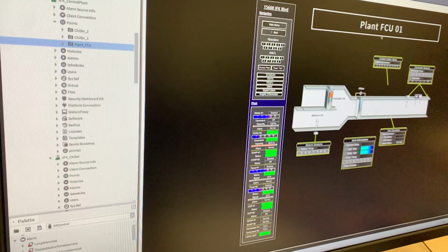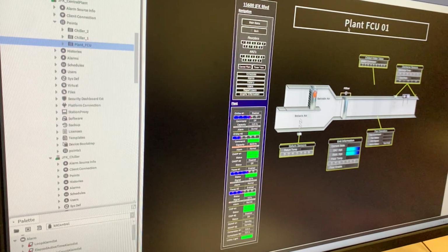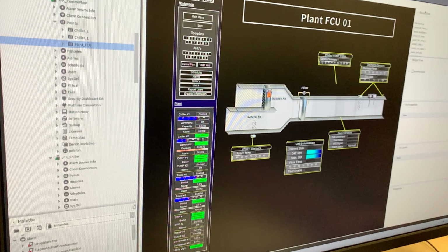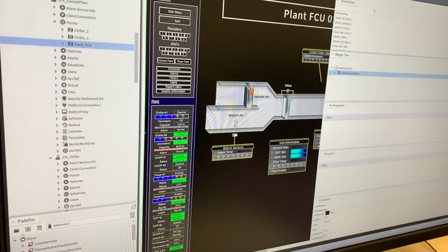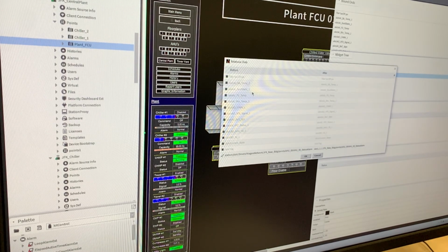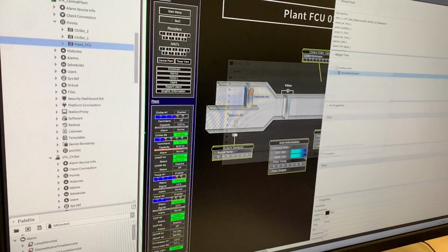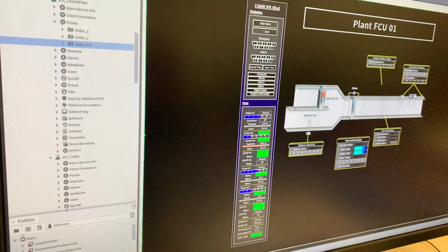When you do a VAV box or a fan power box through Honeywell, the point gives you a tag already built in, to where you can just link it and then relativize it. So I'm gonna show you a quick little thing right here. Since this graphic is the one that's actually being utilized for this point folder, here's this right here. Then we come over to our bound ords. I know you can't really see it because I'm doing all this in the field, but I'll pull it over as much as I possibly can. So here's our bound ords right here. Then I have these two little dots and a slash, and it says relativize ords. Click OK, it'll change it. And now everything will be relativized, so that way you can utilize this graphic for several different things.